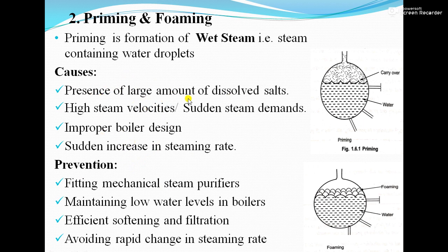Prevention of priming: the presence of large amounts of dissolved salts can be prevented by fitting a mechanical steam purifier and by efficient softening and filtration. High water levels in the boiler can be reduced by maintaining a low water level. Sudden increase in steaming rate can be prevented by avoiding rapid changes in the steaming rate.